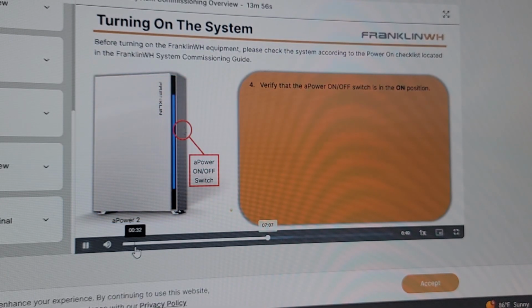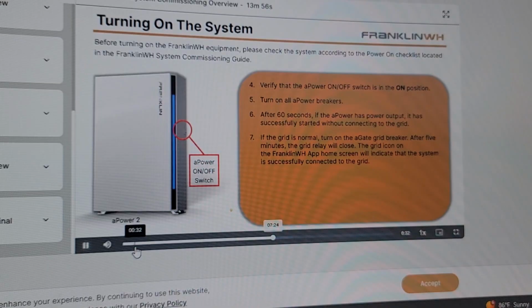Step 4. Verify that the aPower on-off switch is in the on position. Step 5. Turn on all aPower breakers. Step 6. After 60 seconds, if the aPower has power output, it has successfully started without connecting to the grid. Step 7. If the grid is normal, turn on the aGate grid breaker.